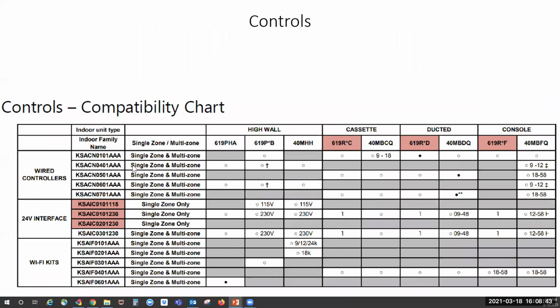Controls and compatibility. You will want to refer to your compatibility chart for your controls to make certain it works with your unit. Not all Wi-Fi controllers work with all indoor systems. Not all wired controllers either. And when I say wired controllers, that is the thermostat that comes with that unit, so it is a communicating thermostat. If you want to use a 24 volt thermostat, you will have to install a 24 volt interface.